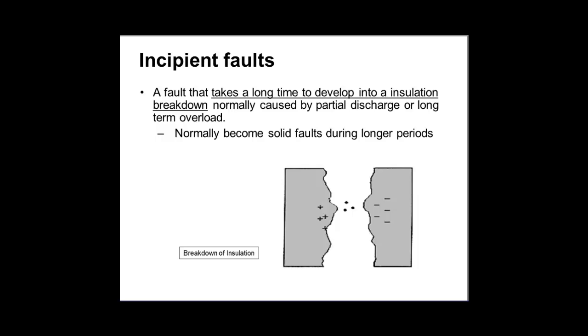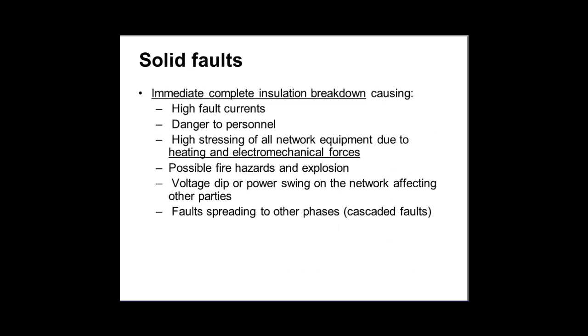So therefore, you need to understand the kind of fault that you have got. If that fault is going to happen somewhere very far from the CBD, the amount of short circuit current could be very low. So in that case, even a fuse protection would be enough. However, when it goes into the central business area, even a three-phase short circuit is a very, very strong, solid fault.